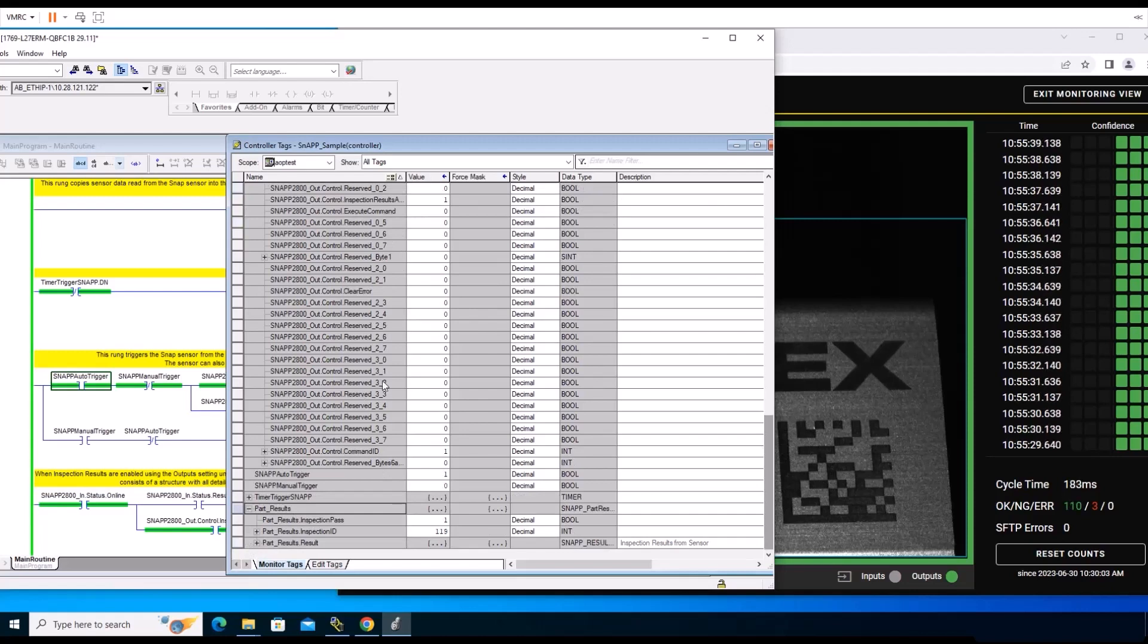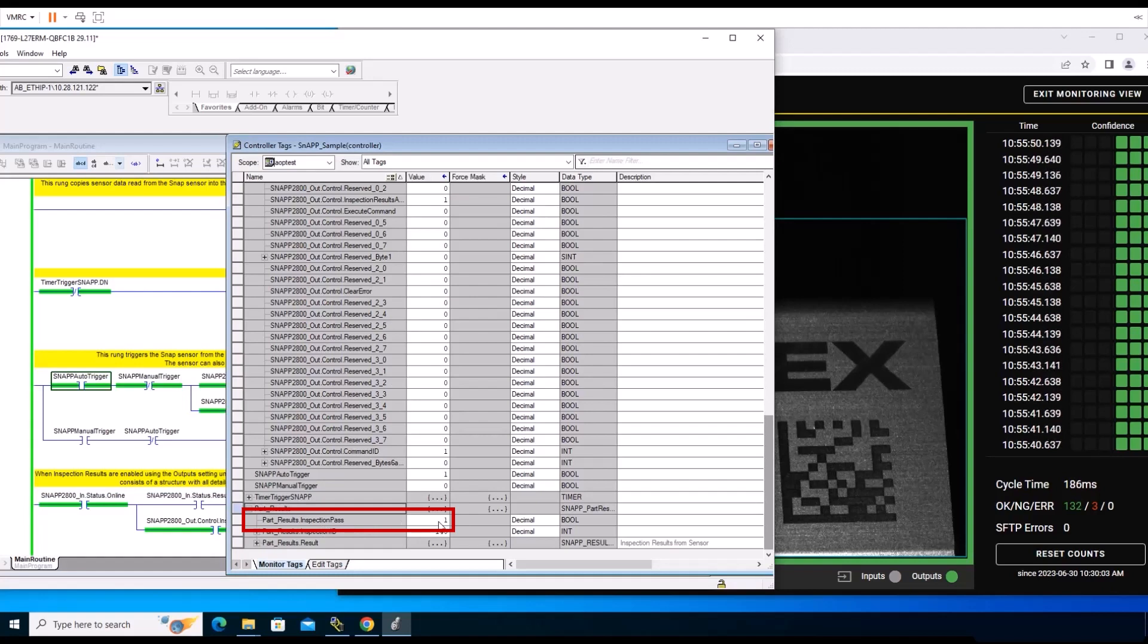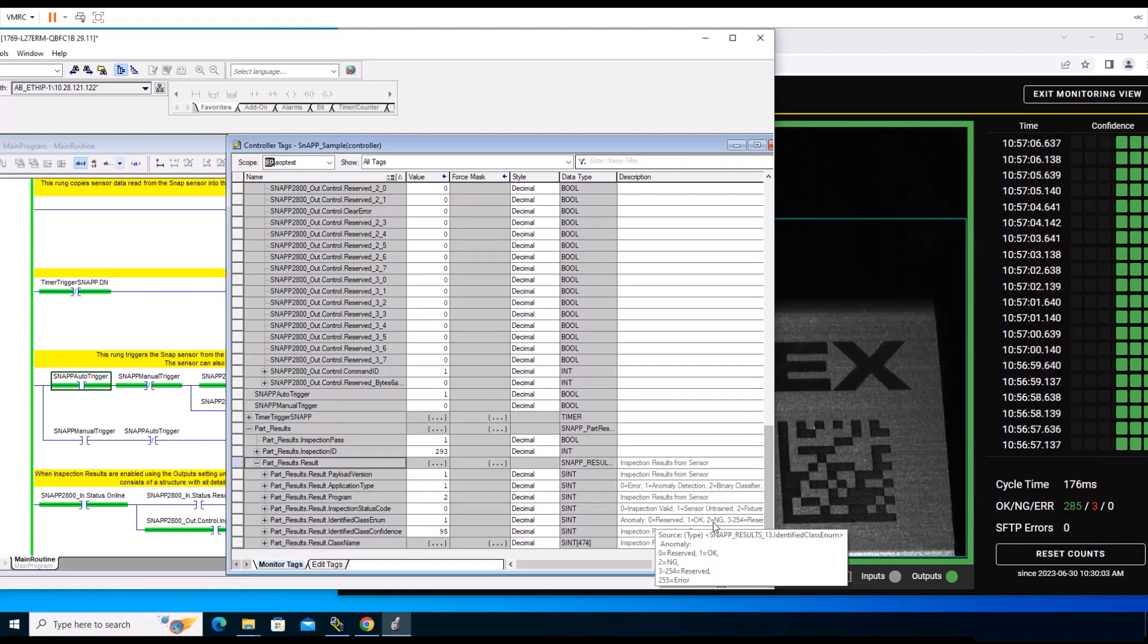At this point, we can see a static image. These results can be found on the last rung on the Status Result rung at the bottom right of the Main Program Main Routine panel. The last inspection result is a pass indicated by the number 1. You can also navigate back to the Controller Tags window and open the Part Results List to see more detailed results. These include application type, inspection status code, and confidence level. For this program, the application type value is 1, which refers to anomaly detection. The inspection status code value is 0, which refers to a valid inspection. To see a no-good result, move an object in front of the part.